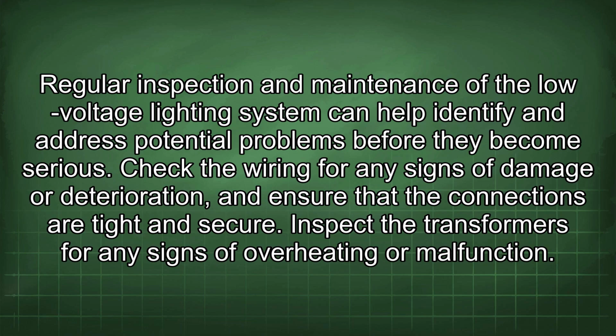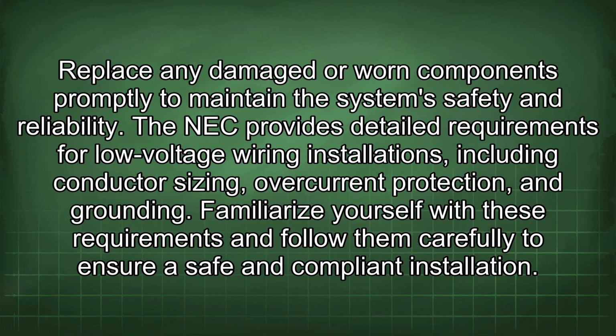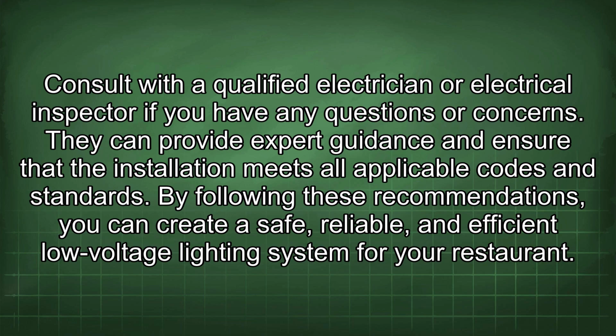Regular inspection and maintenance of the low-voltage lighting system can help identify and address potential problems before they become serious. Check the wiring for any signs of damage or deterioration and ensure that the connections are tight and secure. Inspect the transformers for any signs of overheating or malfunction. Replace any damaged or worn components promptly to maintain the system's safety and reliability. The NEC provides detailed requirements for low-voltage wiring installations, including conductor sizing, overcurrent protection, and grounding. Familiarize yourself with these requirements and follow them carefully to ensure a safe and compliant installation. Consult with a qualified electrician or electrical inspector if you have any questions or concerns. They can provide expert guidance and ensure that the installation meets all applicable codes and standards.